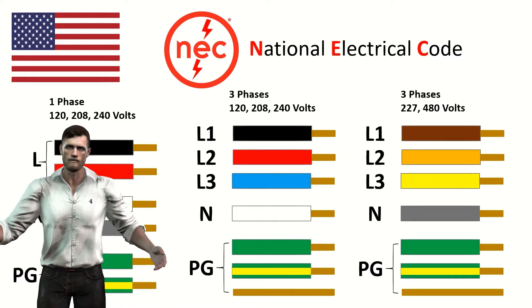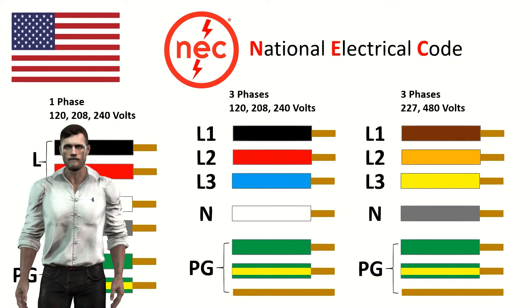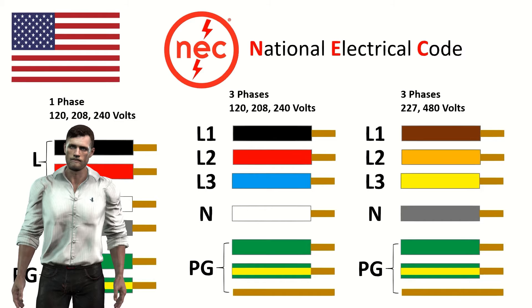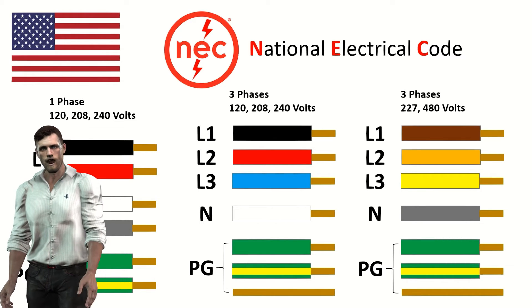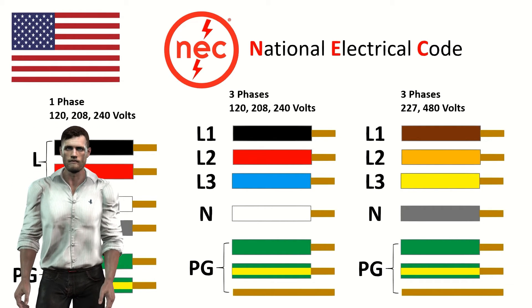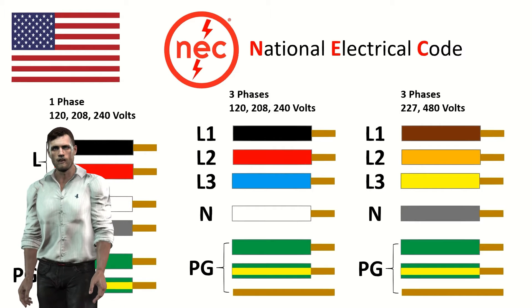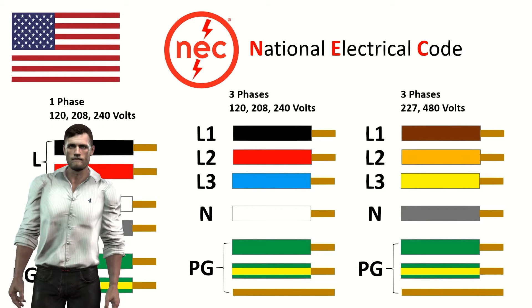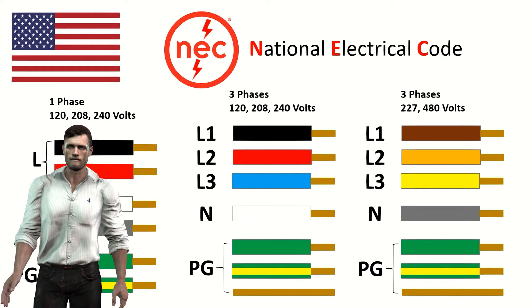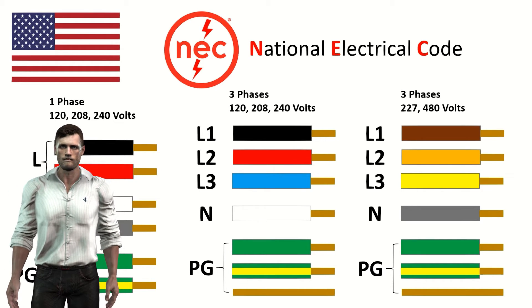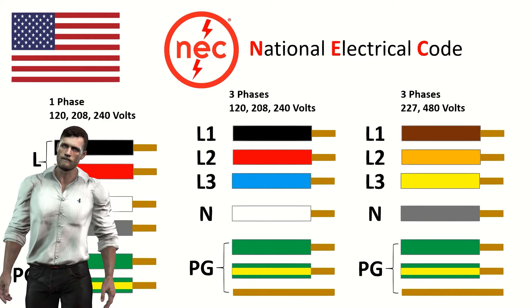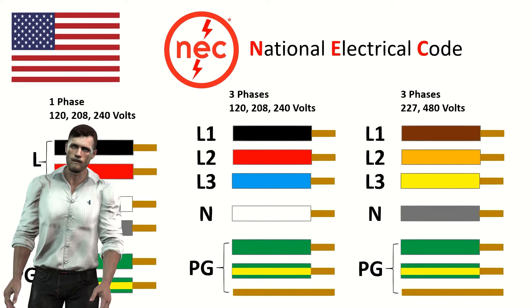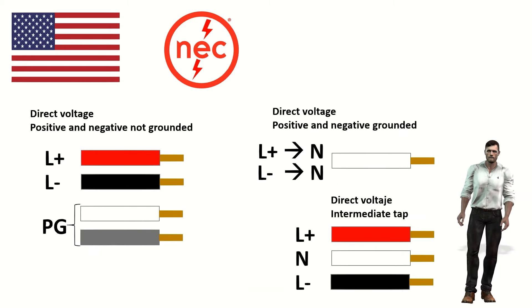For three-phase installations of 277 or 480 volts, used mainly in industry, we have brown for line 1 (L1), orange for line 2 (L2), yellow for line 3 (L3), and gray for neutral (N). The protection or ground wire (PG) again uses the colors green, green with a yellow stripe, or the bare copper wire.